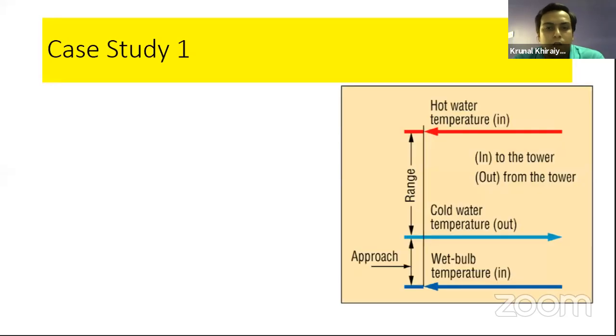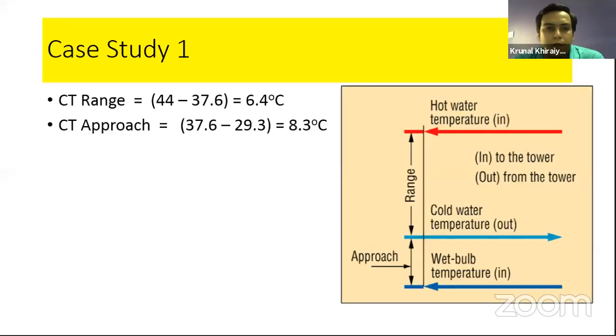Now, moving further, we go for the calculations of range and then approach. The temperature of water which comes from the process heat exchanger is 44. The water we supplied from the pump is 37.6, and the wet bulb temperature of air is 29.3. So we get 6.4 degrees centigrade of CT range, and our cooling tower approach is 8.3.